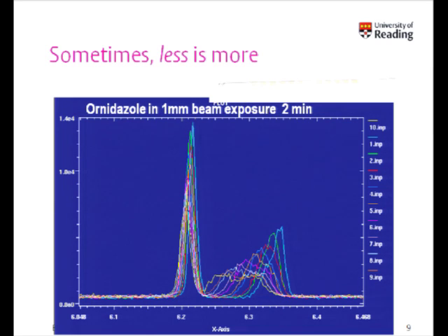Now, if you don't take account of this in advance and you simply put on the sample, open the shutter and disappear for a cup of coffee and come back, then rather than nice sharp diffraction peaks, you'll have some very, very broad splurges, for want of a better word, in your diffraction pattern. You can actually see the sample radiation damage from each exposure on that capillary very clearly, these little brown spots here.